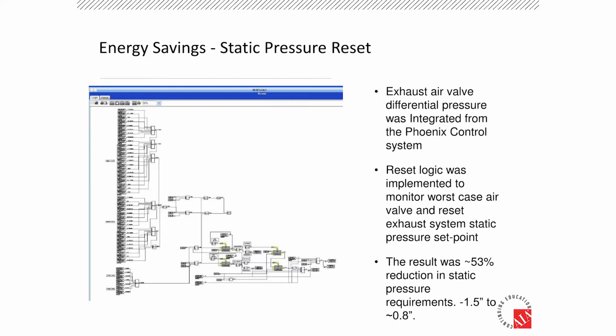They work off of a differential pressure. So the contractor installed differential pressure transducers across all their exhaust air valves and mapped them back to the Phoenix system. Phoenix control valves require a minimum differential pressure to guarantee accuracy over their spring, right? So we brought all those points back, integrated through the system, which is all those data points on the far left side, and we ended up putting in some control logic to look at the worst case scenario box.